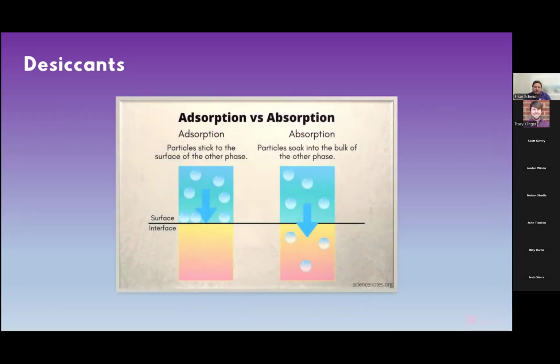Slight difference between solid desiccants and liquid desiccants. A solid desiccant uses an adsorption process, which means that it sticks, but it does not change phase. So it sticks to the solid desiccant versus a liquid desiccant, which is an absorption. We are absorbing the moisture from the air, and it is turning from a gas to a liquid. So we are going through a phase change.